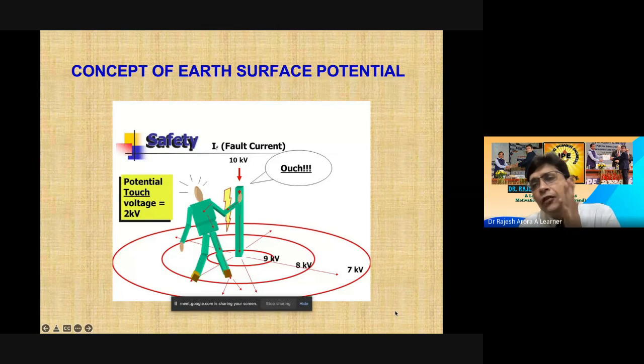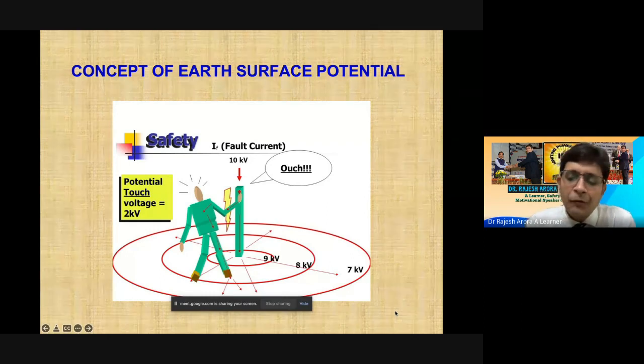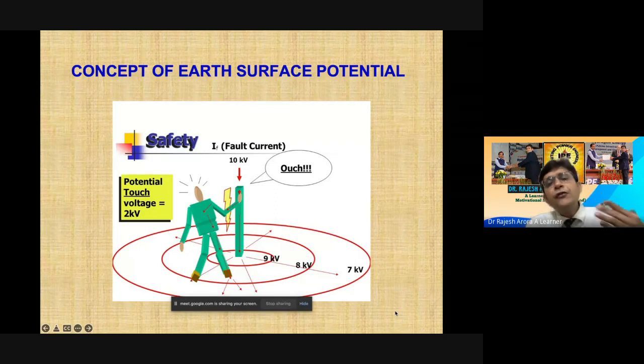If it is more than the tolerable touch potential voltage of your body, you will get a shock. Yes, you will get a shock. And that shock depends on duration, magnitude, frequency, and the path taken by that current through your body. It also depends whether it is AC or DC, low frequency or high frequency, man or woman. Many good documents are available, and you can read IEC 60479 part 1 to part 5 to have more clarity on the effect of fault current or current on human beings and livestock.